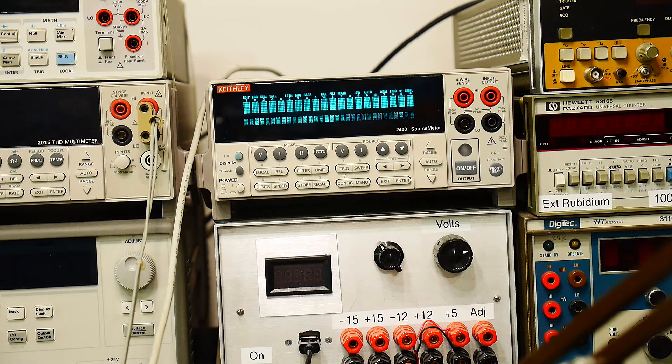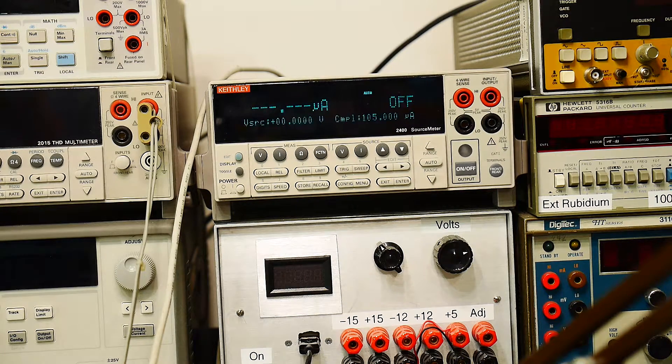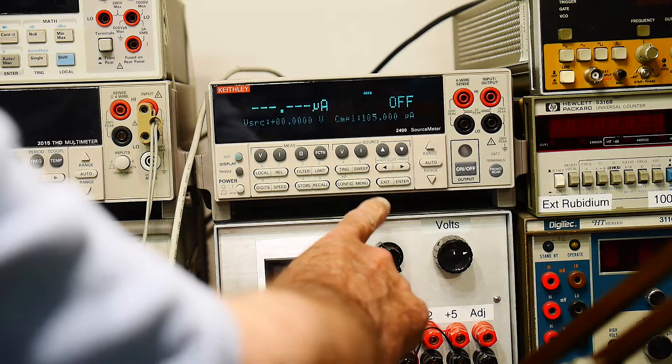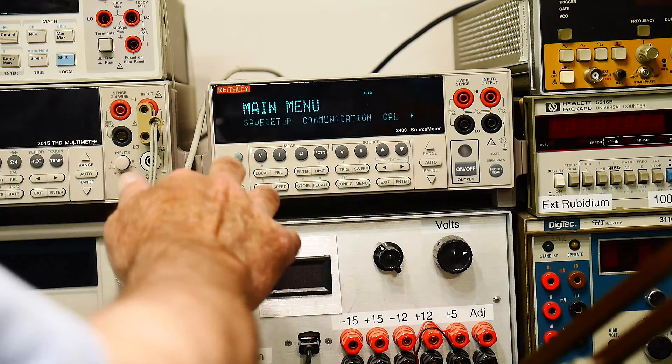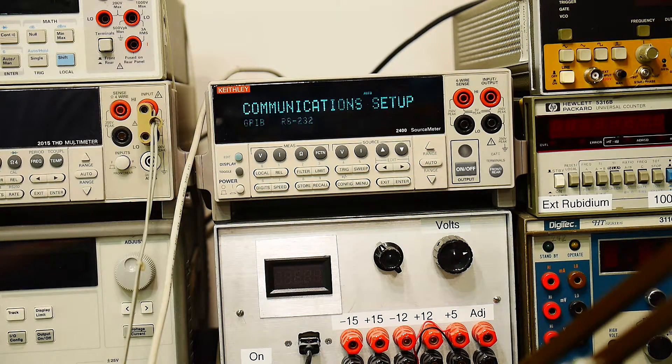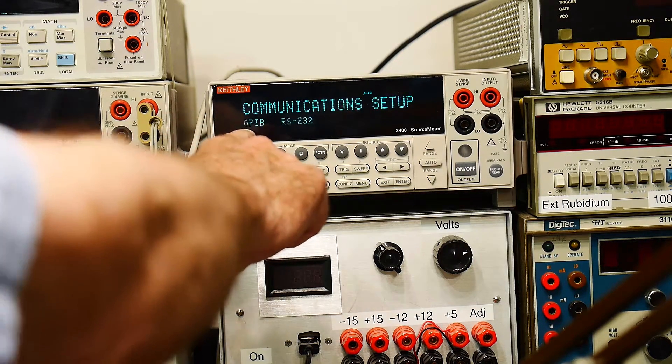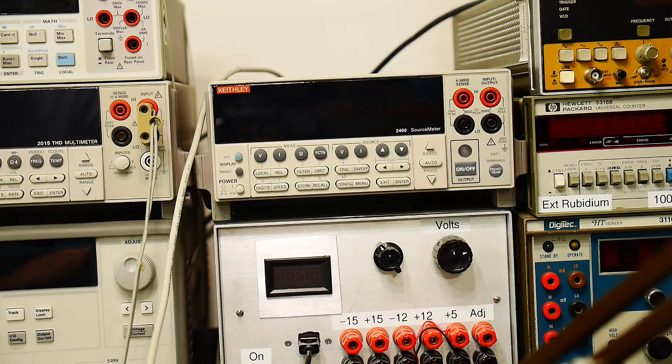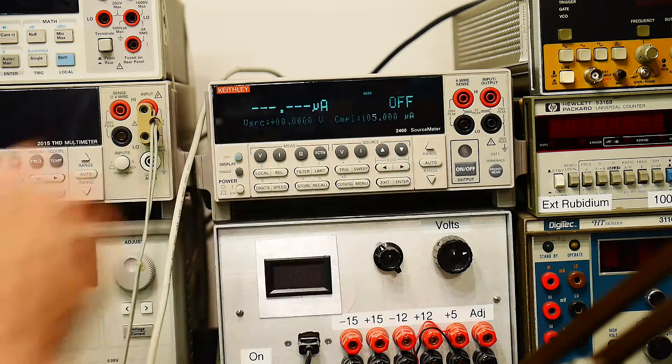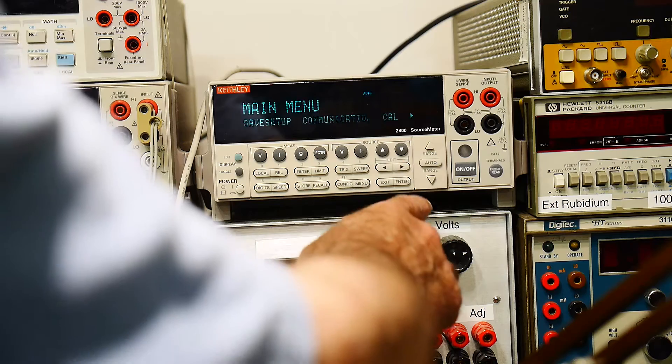I've got the meter back on the bench here. We'll power it up. Model 2400. So before we can use this thing externally, we need to configure it correctly. So we hit the menu button. Communication. We'll arrow over to that. Hit enter. Communication setup is GPIB or RS-232. Right now it's defaulting to GPIB. So we'll come over here to RS-232. Enter. And the device is resetting itself and putting it into RS-232 mode. There we go. So it's RS-232 mode on the front panel.